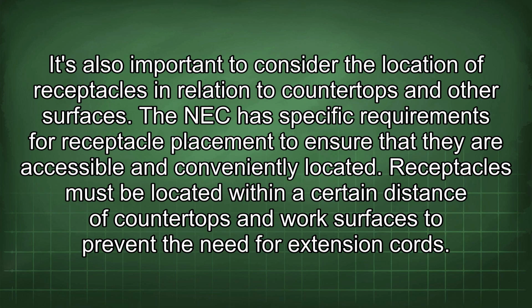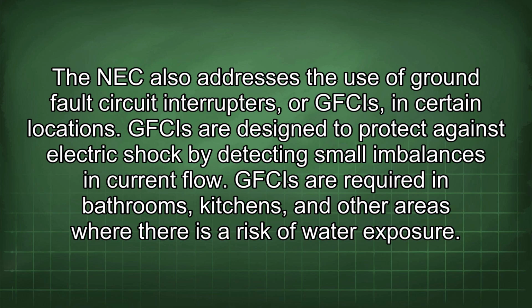It's also important to consider the location of receptacles in relation to countertops and other surfaces. The NEC has specific requirements for receptacle placement to ensure that they are accessible and conveniently located. Receptacles must be located within a certain distance of countertops and work surfaces to prevent the need for extension cords. The NEC also addresses the use of ground fault circuit interrupters, or GFCIs, in certain locations. GFCIs are designed to protect against electric shock by detecting small imbalances in current flow. GFCIs are required in bathrooms, kitchens, and other areas where there is a risk of water exposure.